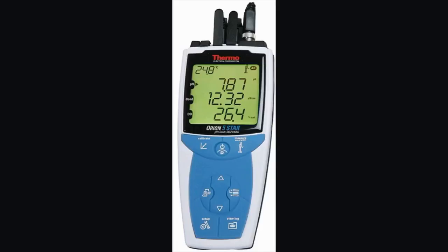And again, this was approximately 1 hour after the loggers had been in the water and logged about 4 data points. So we're going to use that information to post-process our data when we pull the logger out. When we go back to the site, we will bring a dissolved oxygen probe as well, and we will take a measurement of both conductivity and dissolved oxygen prior to pulling that logger out of the water. Always a good idea to use a precision meter to take a measurement after the logger is stabilized at the beginning of your deployment, and then again at the end of your deployment before you pull the logger out of the water to give you the ability to calibrate your data if you need to.